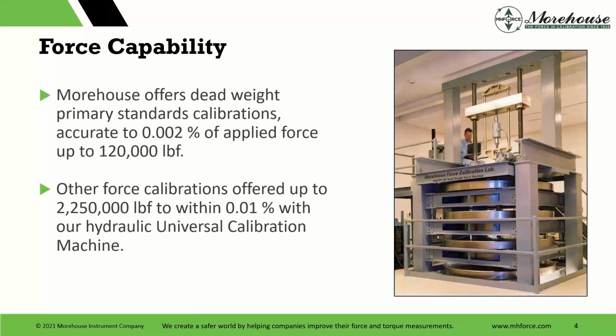So what makes us different or unique is we have dead weight. We are a primary lab, which means we offer dead weight calibration. Being a primary lab, we offer calibrations with super low uncertainties, like 20 parts per million of applied force to 120,000 pounds of force, or a little over 500 kilonewtons. We also go up to 10 meganewtons within 0.01%, and 10 meganewtons is about 2.25 million pounds of force. So really, really high level force. Primary lab up to 500 plus kilonewtons, or 120,000 pounds.